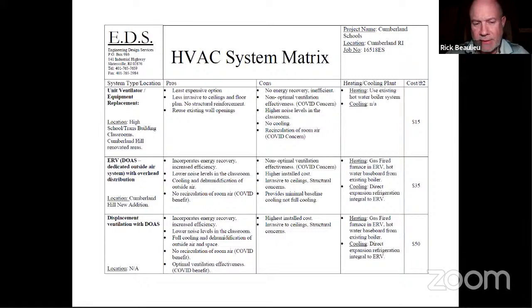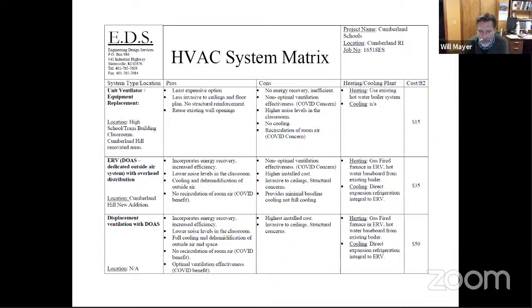So the displacement ventilation, basically, you're bringing in fresh air and exhausting it completely. And based on the sizing of the system, that can happen one or many times per minute, per hour, what have you. Correct? Right. Yeah, it's certainly going to meet the minimum requirements of ASHRAE and CDC and all that. Usually it's in excess of that. The good thing about school ventilation, because it's fairly densely occupied, is that when you're meeting the code requirements for ventilation, you're meeting all of these ASHRAE guidelines that are in place.